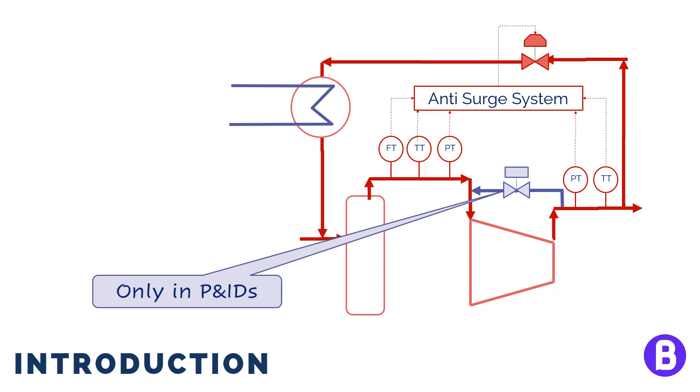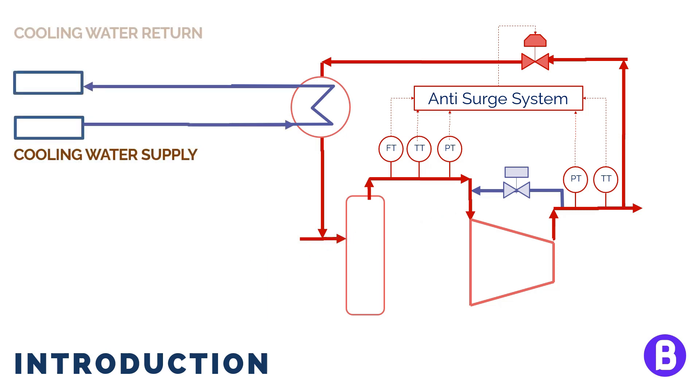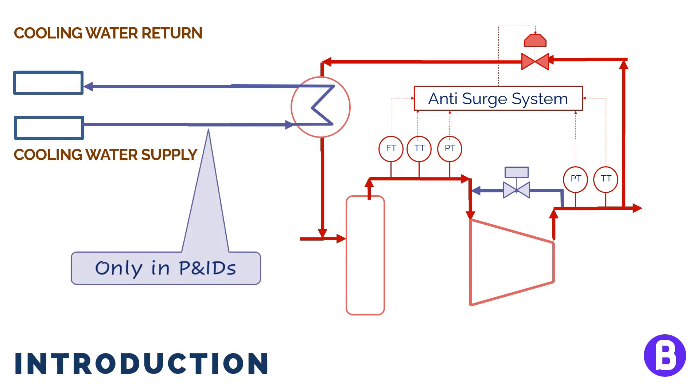In addition, P&ID should consider all utility and effluent lines. For example, in case of a PFD, cooling water lines are not always shown on a water cooler. But when we prepare a P&ID, the cooling water supply or return lines should be shown along with their source.